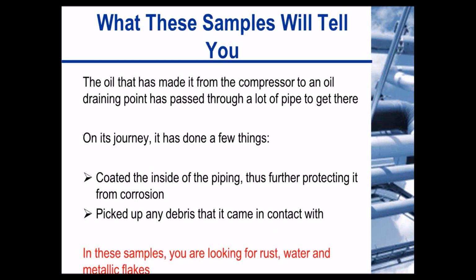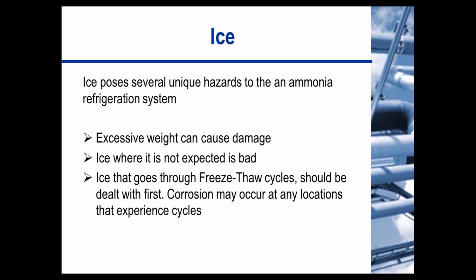So let's consider ice for a moment. Ice poses several unique hazards to the ammonia refrigeration system. Excessive ice can result in excessive weight on your system and damage it. Ice where it's not expected, in general, is a bad thing, especially ice that goes through freeze and thaw cycles. These should be dealt with first. These freeze-thaw cycles are points where corrosion would occur and is actually expected to occur.